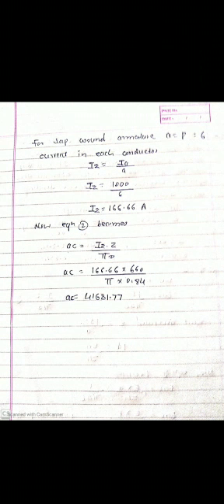Now substituting into equation 2: AC = I_Z times Z divided by pi D. Putting in I_Z = 166.67, Z = 660, D = 0.84, we get AC = 41681.77 ampere-conductors per metre. So that is the specific electric loading. Like that we calculate the values of specific magnetic loading and specific electric loading.